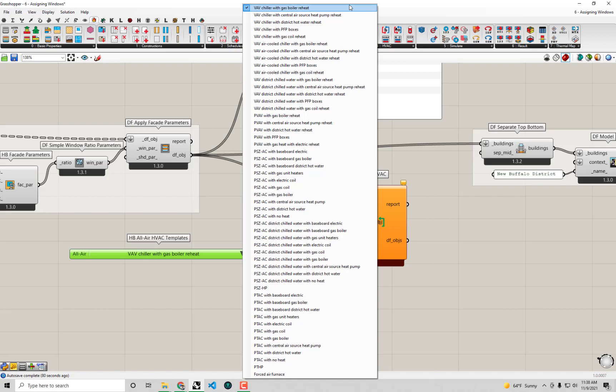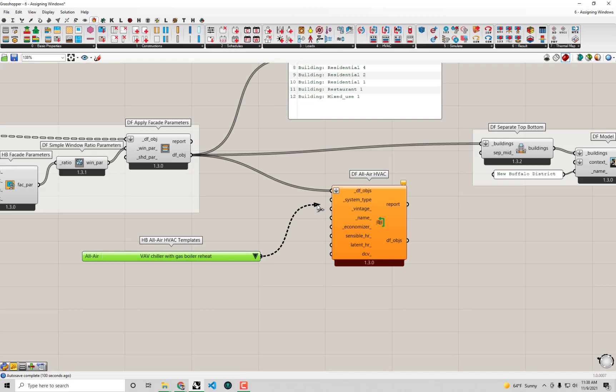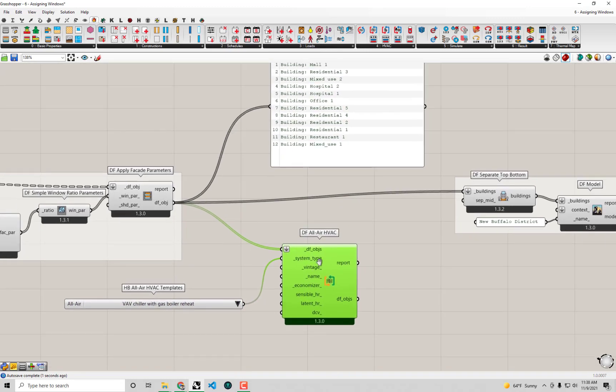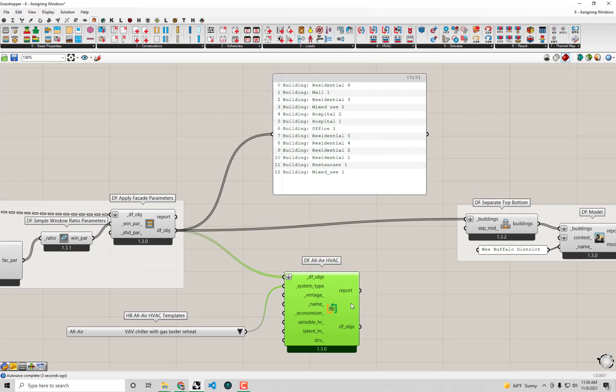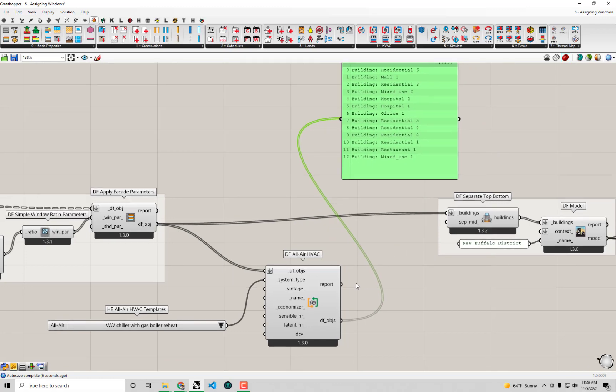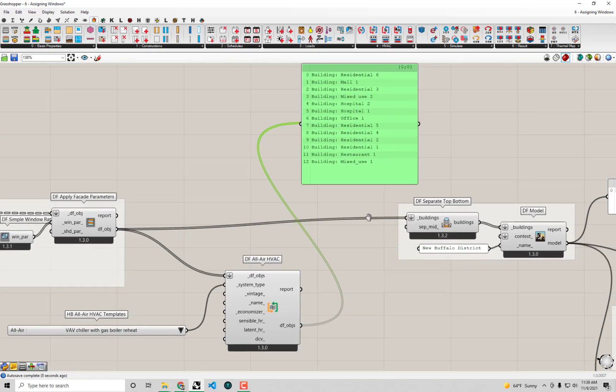I think actually, though, I'm going to take the one that we already have selected right now, this VAV chiller with gas boiler reheat. I know this is what the baseline model is for any commercial building over five stories. I know that the code recommends that you use this VAV system with gas reheat. So if I go and connect this up to our system type here, you see that the component's going to run, and out of it we're going to just get the same thing that we got in, except just that the detailed HVAC systems have been added to this.